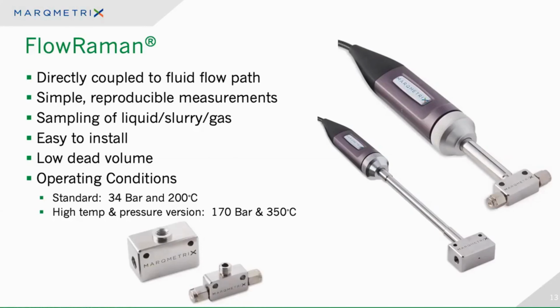And we can work at very different, very high pressures, in this case, 170 bar at 350 C with our process probe. And with our standard probe, it still has pretty good capabilities at 34 bar and 200 degrees C. What we're doing is very low dead volumes. In this case, we have about 200 microliters of total internal volume with our standard probe. It was actually designed with some of the work that we're doing in continuous flow reactors.